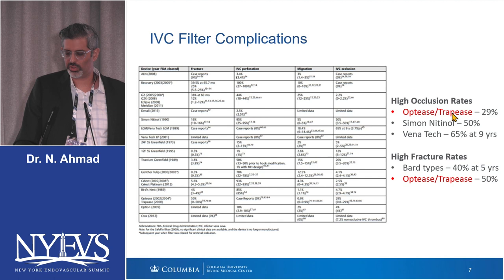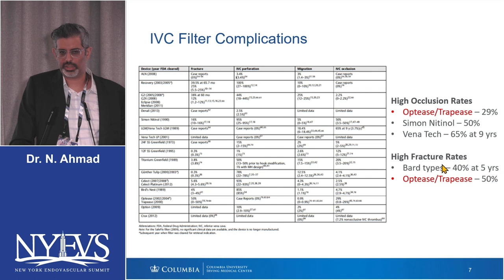IVC filter complications: OptEase and TrapEase filters are known to have high occlusion rates, and certain filters — especially Bard types — tend to have high fracture rates.